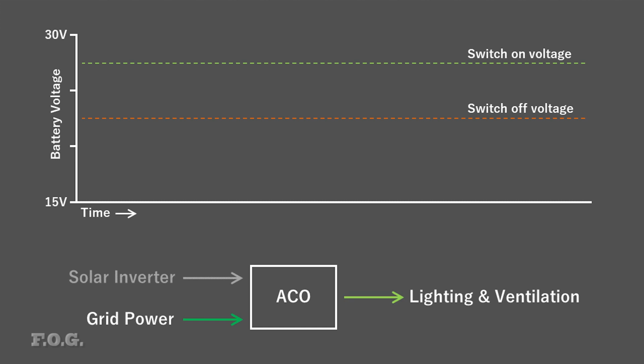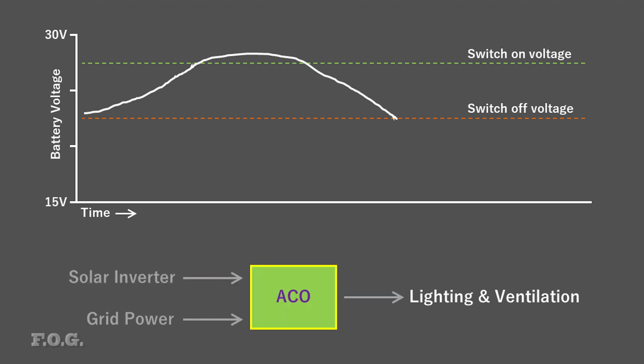On a different note, another interesting part of this puzzle is the mains automatic changeover unit, or ACO. It simply looks at the DC bus voltage, and when the voltage exceeds a configured value, it switches to using power from the inverter. Following that, once the battery discharges and the voltage drops below another configured value, it switches back to using grid power.